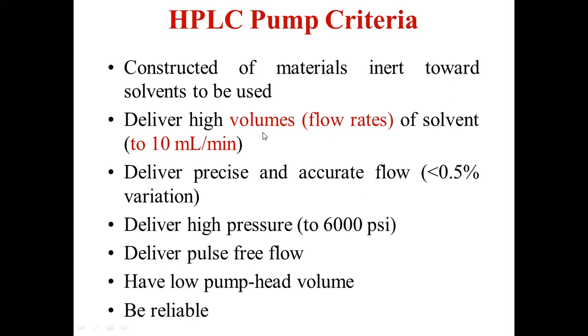Another requirement is that the pump must have the ability to create a flow rate of at least 10 ml per minute. So in a minute, at least 10 ml of the mobile phase must be passed towards the chromatography column. This is the requirement of a pump while choosing it. And it should deliver precise and accurate flow with less than 0.5% relative error. The relative error between two neighboring flows must be 0.5%. The variation should be 0.5%.